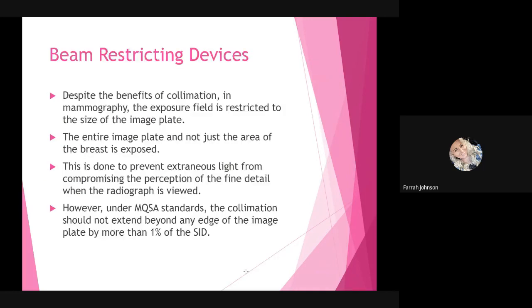Then that brings us to beam restricting devices, so this is going to be our collimation. Despite the benefits of collimation, in mammography, the exposure field is restricted to the size of the imaging plate. The entire image plate and not just the area of the breast is exposed, which is why on mammograms for a medium-sized breast, anterior to that breast tissue, you'll see black, and that's the rest of that image plate being exposed.